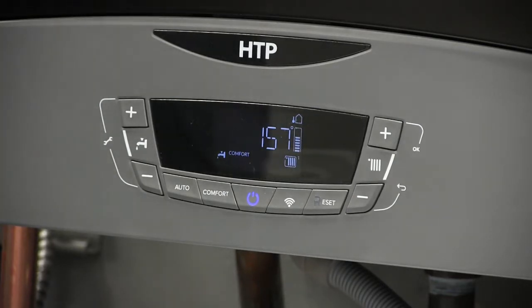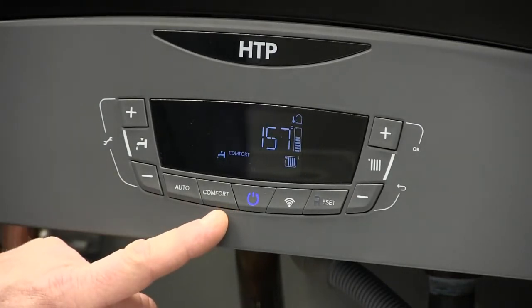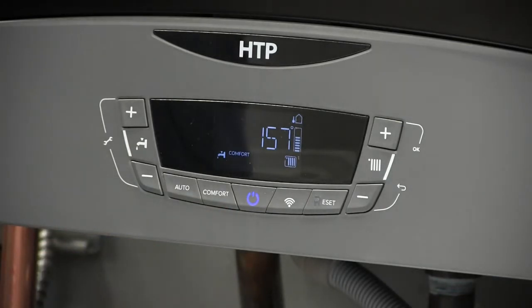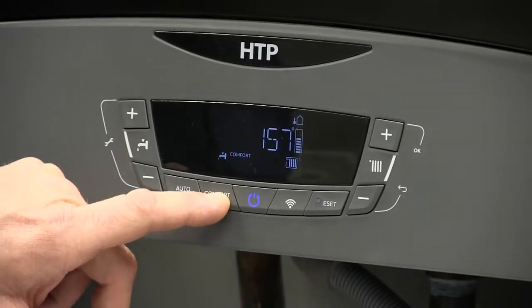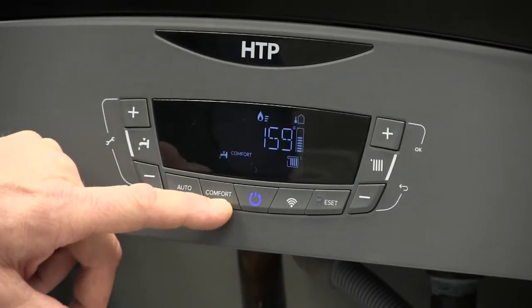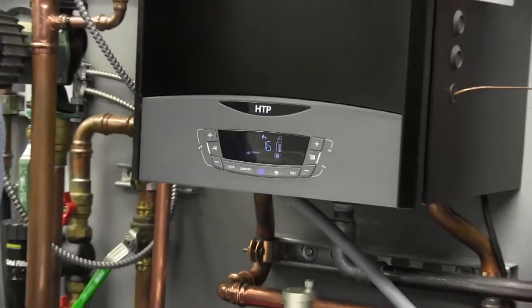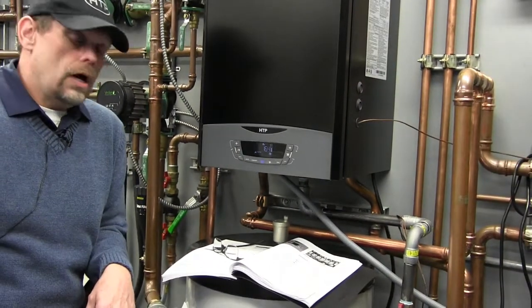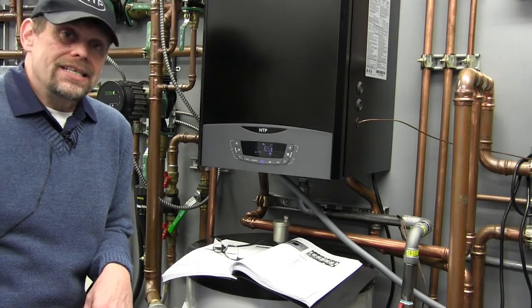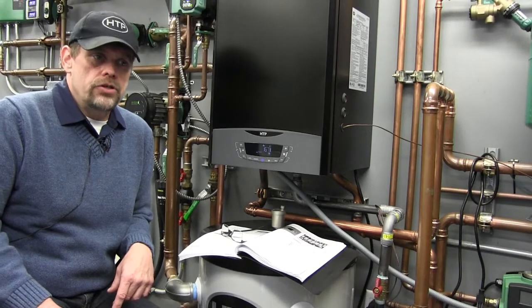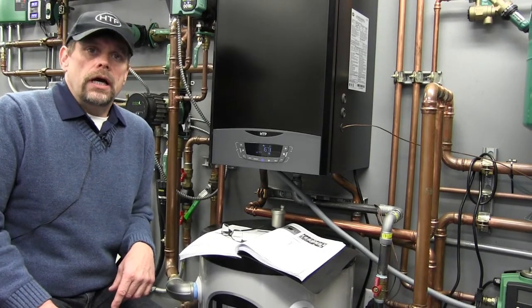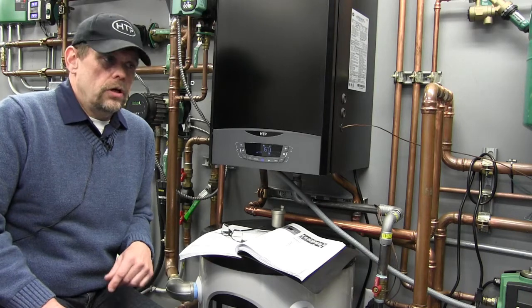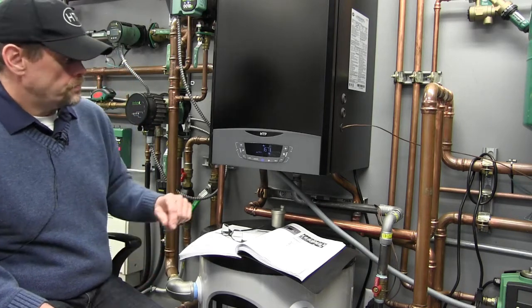The next button that we look at would be the comfort button. In a boiler-only application, the comfort button does absolutely nothing. I have a boiler only here. You press the button, nothing happens. However, if this was a combi boiler, the comfort button in essence engages a low limit function. It maintains a temperature in the secondary heat exchanger or the plate exchanger for domestic hot water production.